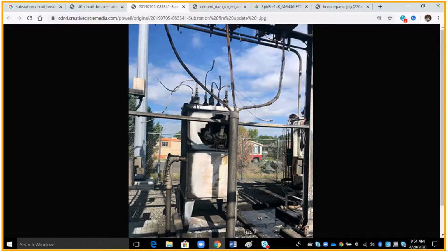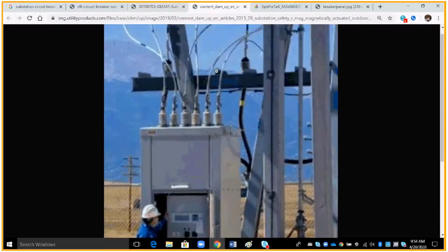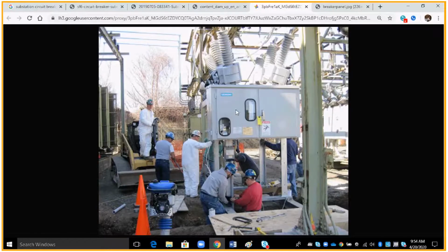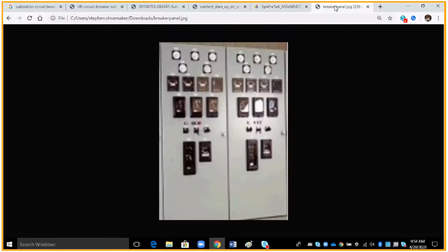There's one. You can't see it here. This typically goes, you see this pipe right here. I'm taking CT readings out of the breaker, and you see this pipe that's going up to the left hand side. That's going to my relay panel. So that's all my low current, transformed current data that's going to the relay. Can't see it in this one. This one isn't even wired yet, so they're not taking it to the relay panel yet. And this is the actual relay panel. This can be inside the substation, inside a substation house or enclosure, or it could be right inside the breaker. The picture that you're seeing right here is in a substation house complex.